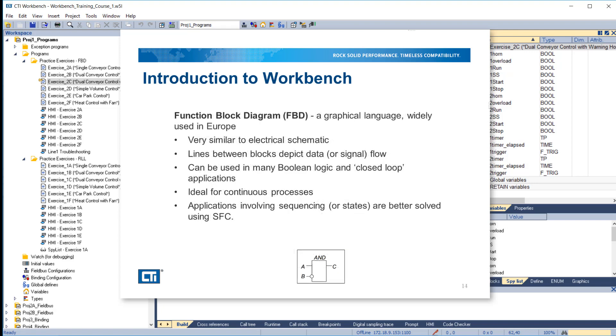Function block diagram is a graphical language which is widely used in Europe. It is very similar to an electrical schematic. Lines between blocks depict data or signal flow. It can be used in many Boolean logic and closed-loop applications. It is ideal for continuous processes. Applications involving sequencing or states are better solved using SFC.